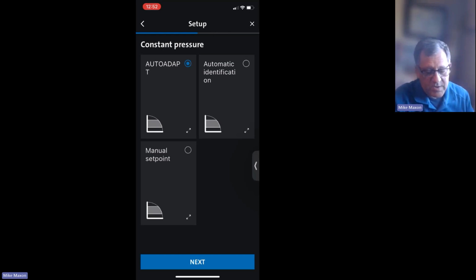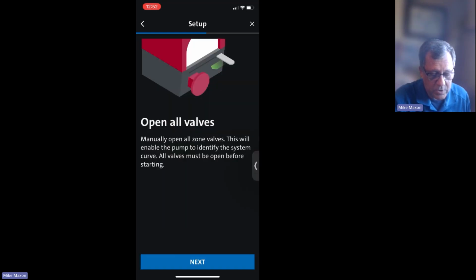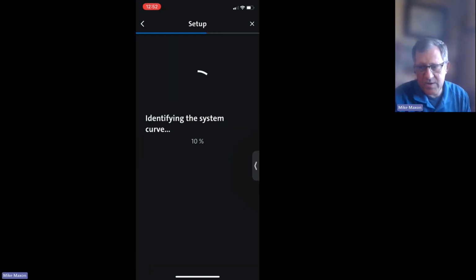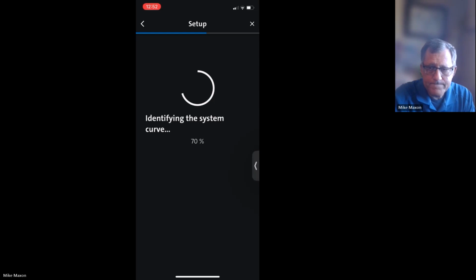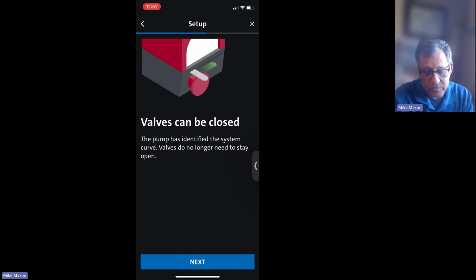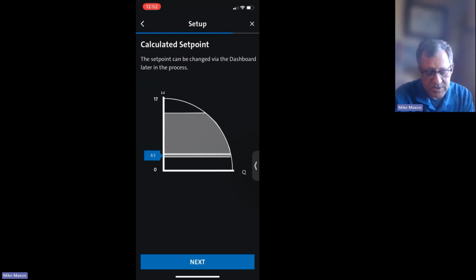Yep. Or automatic identification. Automatic identification is a little process where it's going to tell you, okay, go manually open up all the valves. And then it's going to run to find that duty point for all valves open. Oh, whoa, you're kidding, right? No. It's okay. So basically what you're stating is when you first install the pump, make sure all of your zone valves are open so that it knows its worst case scenario. And then it will actually identify its own set point. The instructions right before this screen, I mean, it didn't show it long enough, but it says, go open up all the valves. Well, here now it says, okay, I ran the test. Go ahead and go close all your valves now. So it's walking you through it. And then it says, okay, with all your valves open, this is where you need to be. There's your set point.